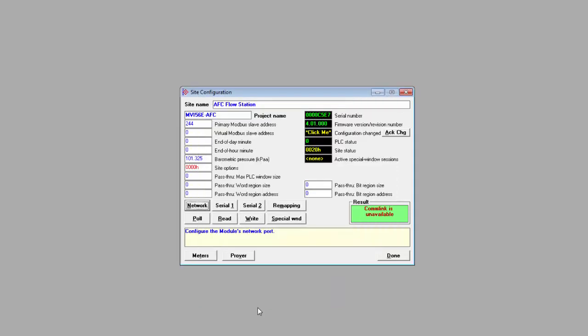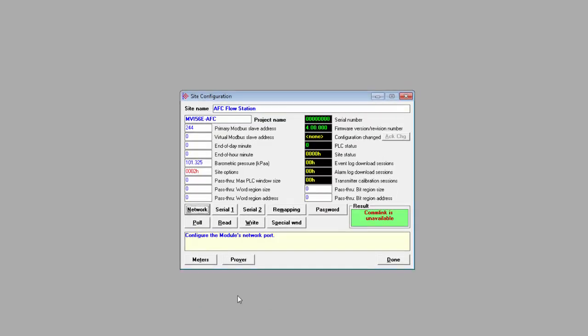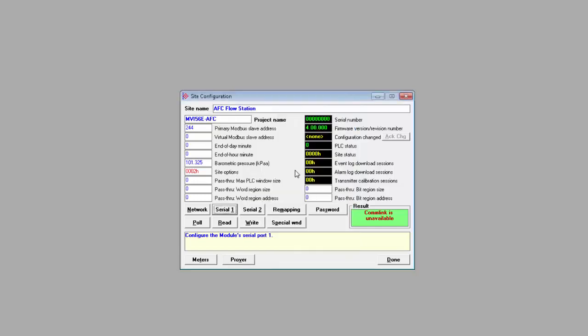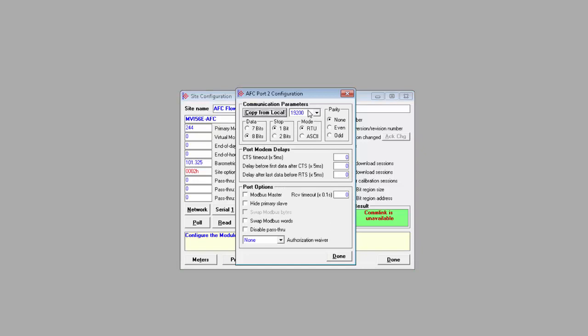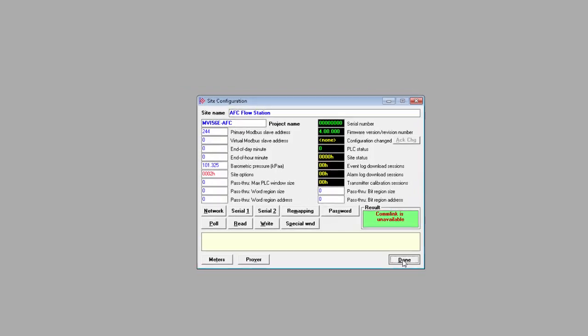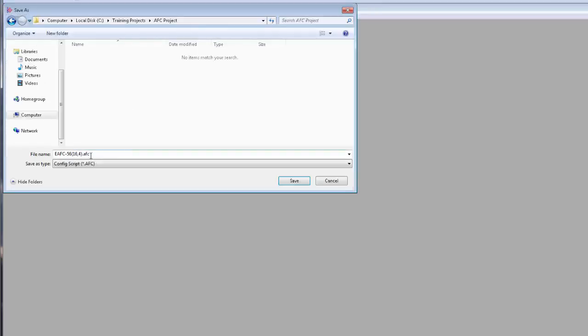I'm not changing anything else, so I'll just hit OK. As for Serial 1 and Serial 2, when you click on those, you get a window with the serial settings for the two serial ports. Port 1 is used for Modbus communication so that the EAFC Manager software can always communicate with the primary slave. The Modbus Master option is only available on Serial Port 2. Just make your changes and hit Done. You can hit Done on the Site Configuration window and this will close the window and temporarily save the settings. You will need to save your project before closing EAFC Manager though, otherwise all your changes will be discarded.